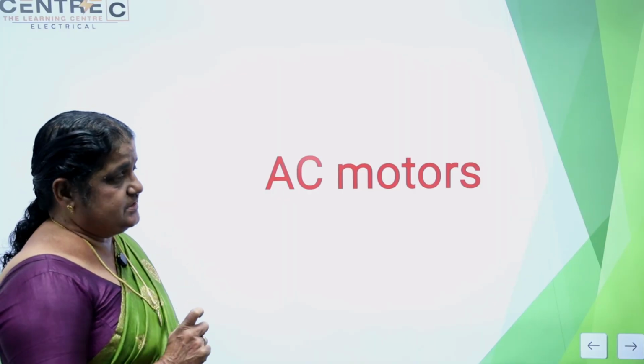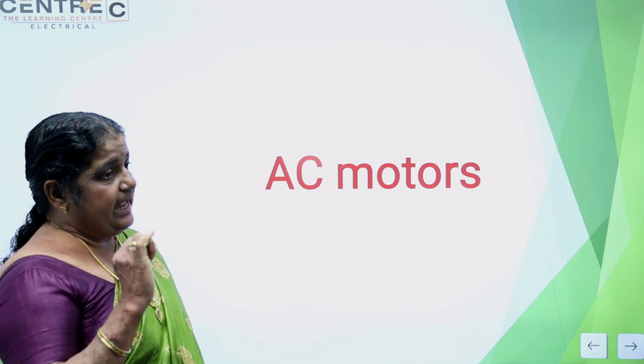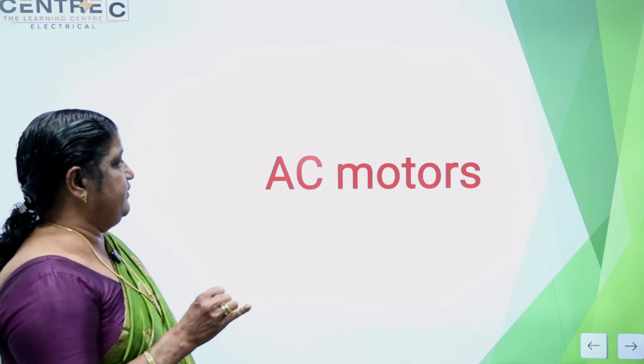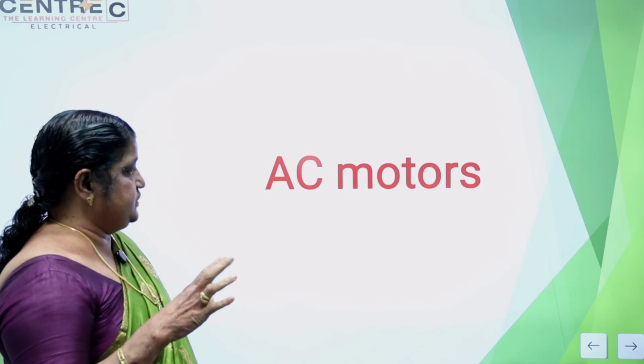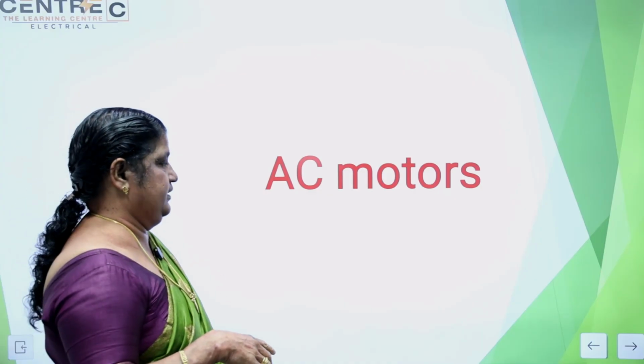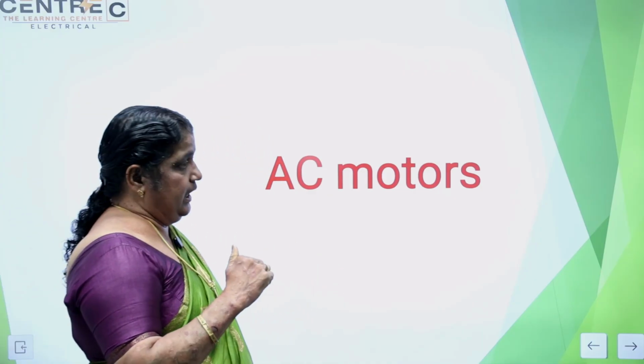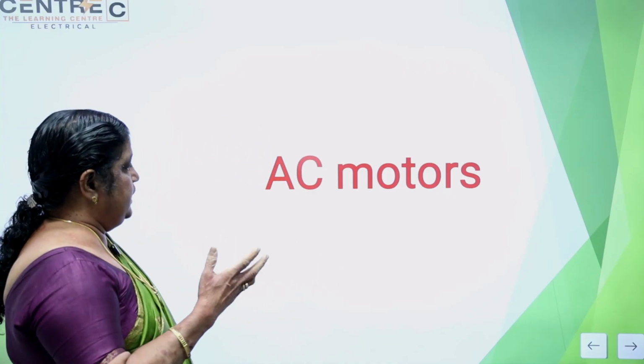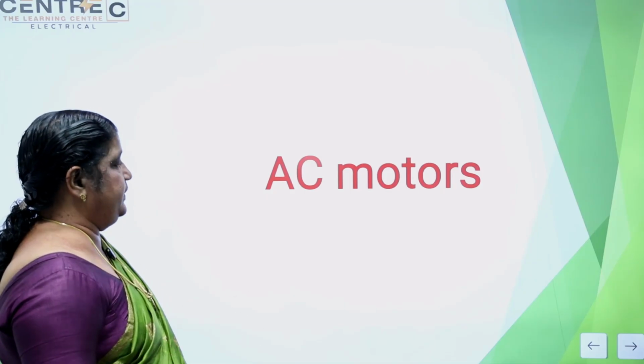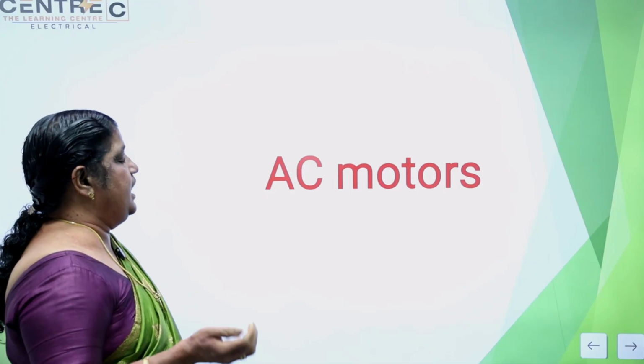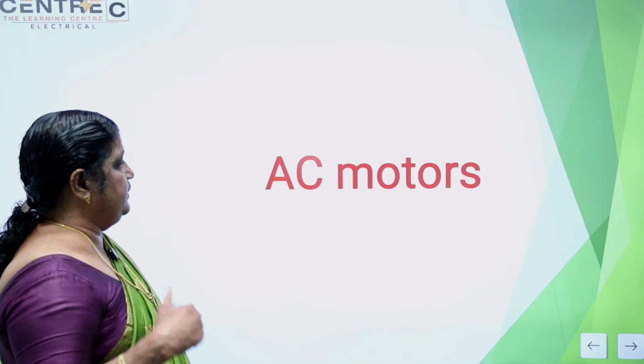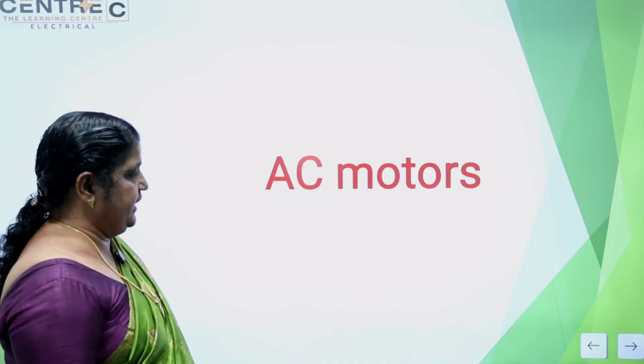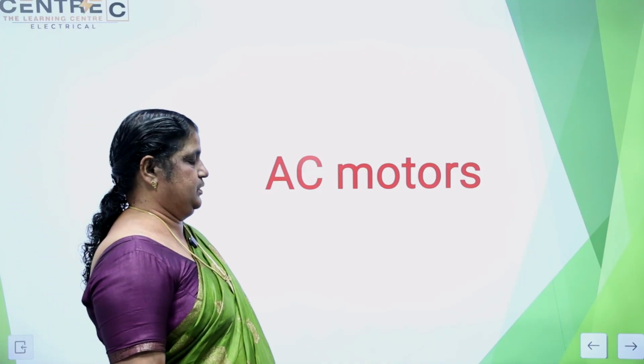Then Hopkinson test. Efficiency depends upon whether it is a motor or generator, and different equations are there. In the case of motor, it is input minus losses divided by input. In the case of generator, it is output divided by output plus losses. The basic equation is output by input.